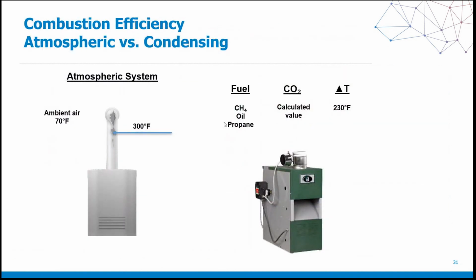Combustion efficiency, atmospheric versus condensing. Again, we have these two different types of systems, and both behave a little bit differently when it comes to measuring combustion efficiency. When we talk about combustion efficiency, whether it's for atmospheric or condensing, we're talking about three major things. The first is fuel. The second one is carbon dioxide. And the third one is delta T.